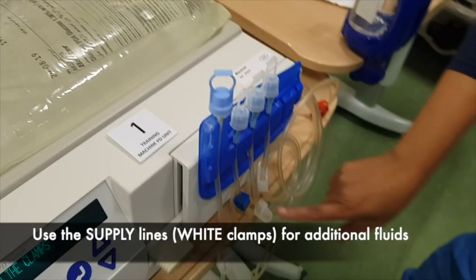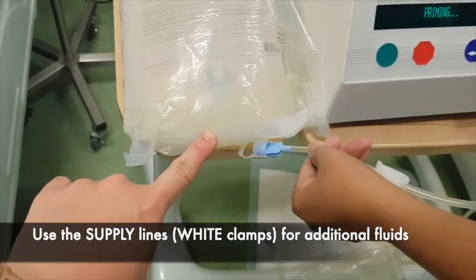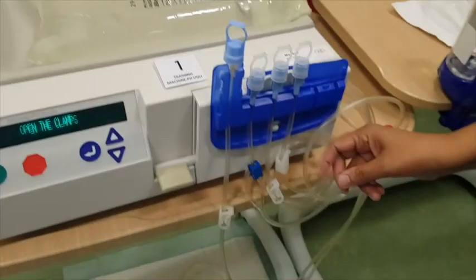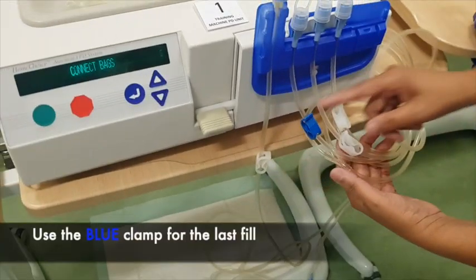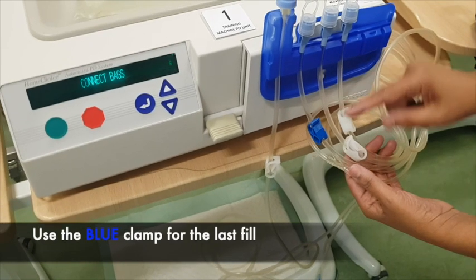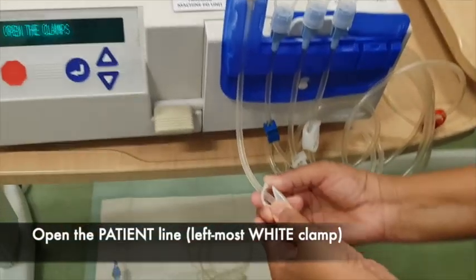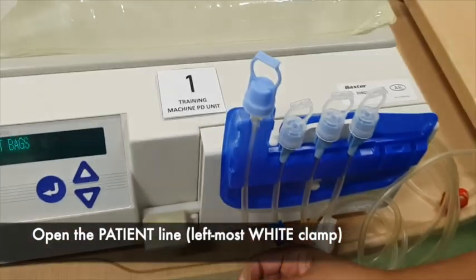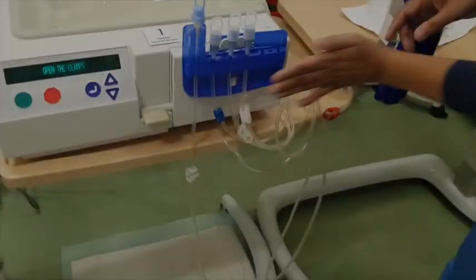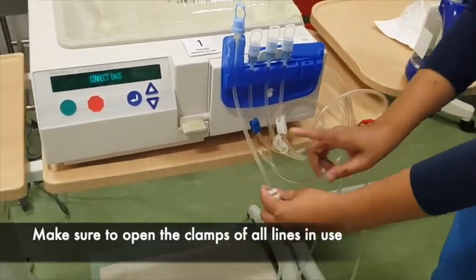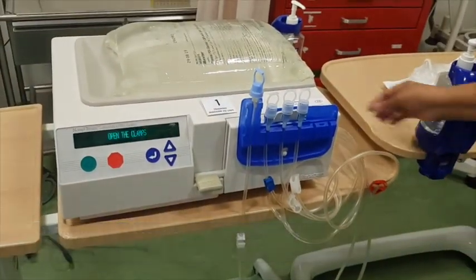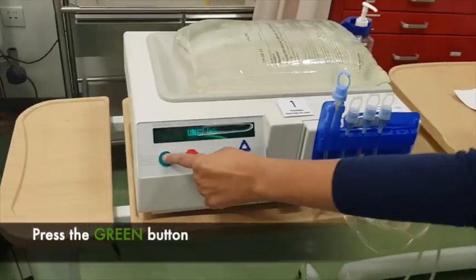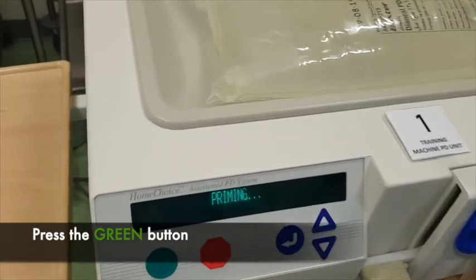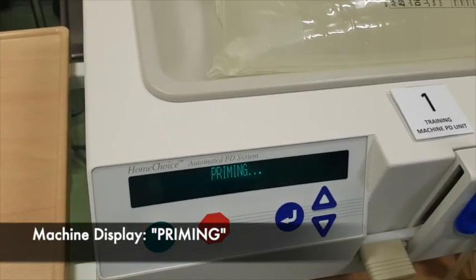You can also connect the supply lines, or the ones with the white clamps, for additional fluids if it is prescribed. If the dialysis prescription requires a last fill, then you can utilize the line with the blue clamp. Next, proceed to open the patient line, which is located at the leftmost corner of the organizer. At this point, make a final check and make sure that all the clamps for the used lines are open. Then, press the green button. The machine will then proceed to priming.